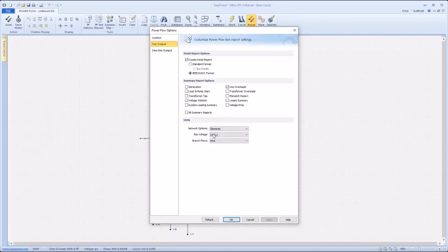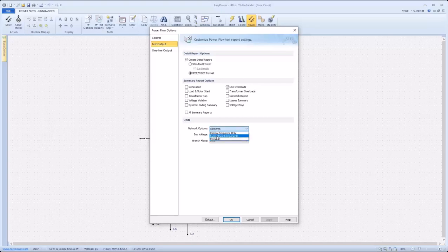The units section is used to designate the units the report will use to display results. There are options for bus voltage and branch flows with a variety of options. The network option dropdown specifies the report format. Positive sequence only will include only results using positive sequence quantities, while symmetrical components will use all three symmetrical component values: positive, negative, and zero sequence. Finally, the elements option reports quantities for each phase A, B, C, and N.